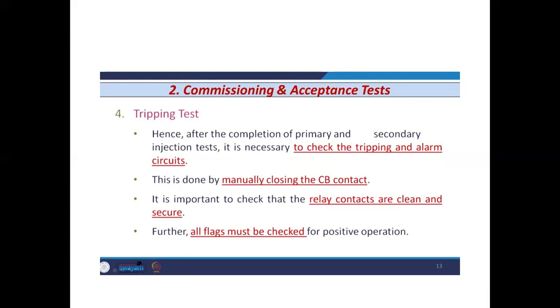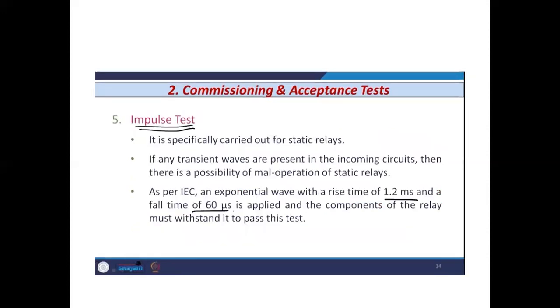It is important to check that the relay contacts are clean and secure. Further, all flags must be checked for positive operation, so that the proper operation can be checked by using the flags provided by the manufacturers. The fifth one is the impulse test. It is specially carried out for the static relays. In the previous lecture, we discussed some tests performed by manufacturers for the dynamic relays, but this test is especially the case for the static relays.